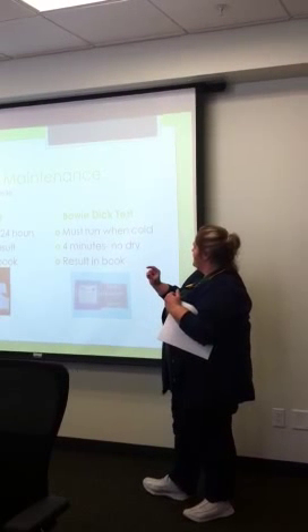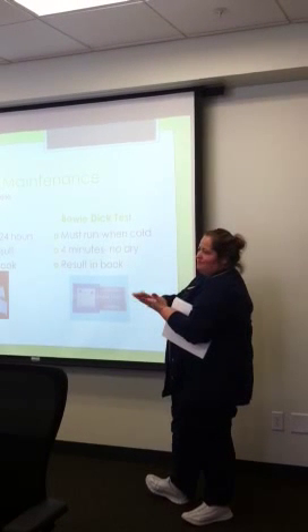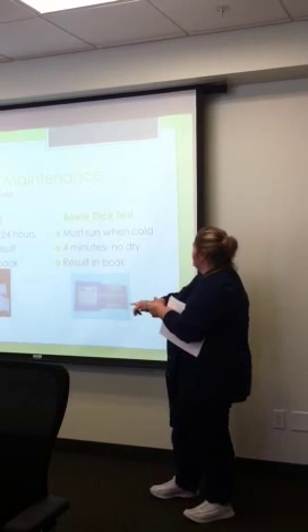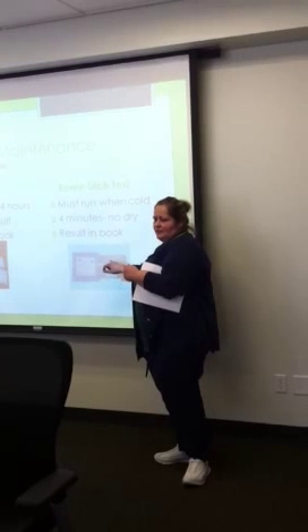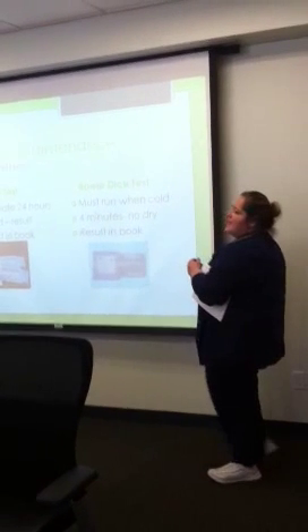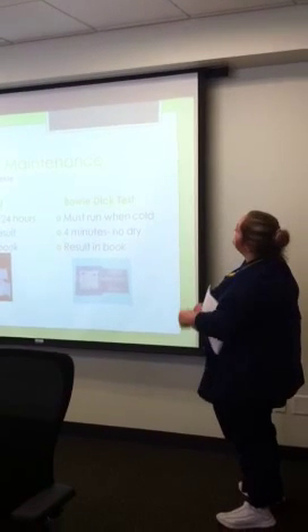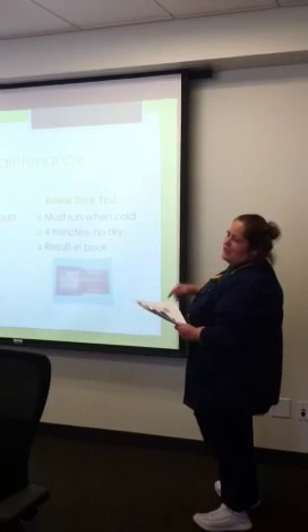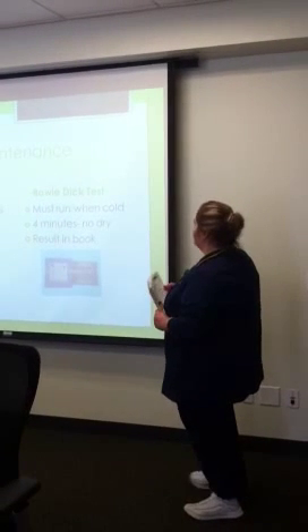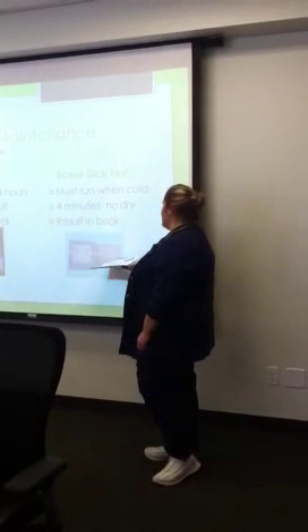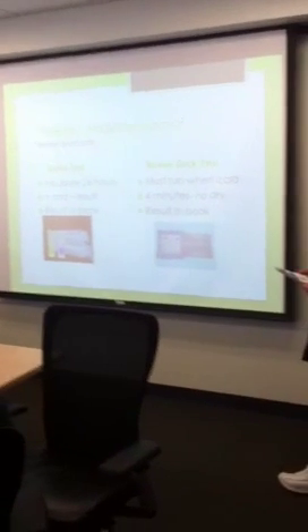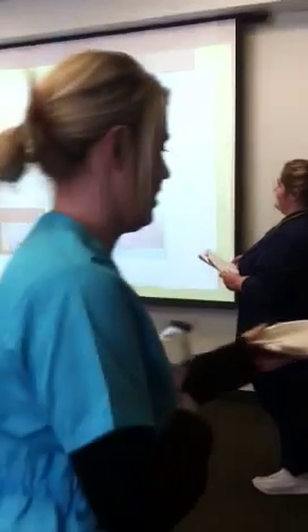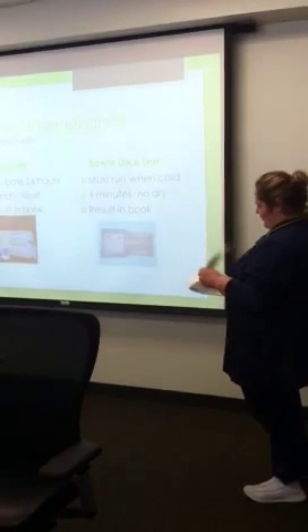It's a packet about this thick, very densely packed with papers and sponges, and in the middle of it is this paper here, and what it's doing is just showing that it got hot enough to turn this indicator black. We run that once a week, and that's the one where I have to change the settings on the machine. So you guys don't have to worry about that, but it's just a 4-minute cycle with no dry time, and again, it's just another check that the sterilization is working. If any of these were to fail, we have a whole policy set up where we have to send the machine in and run like 6 tests on it, so hopefully the machine never fails.